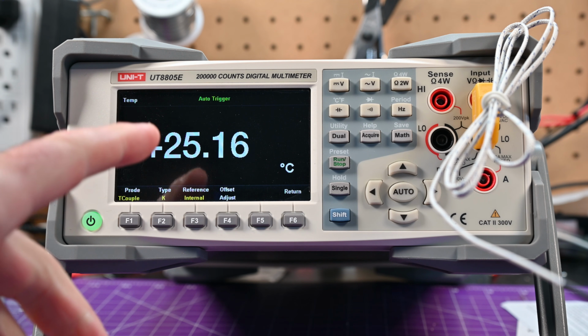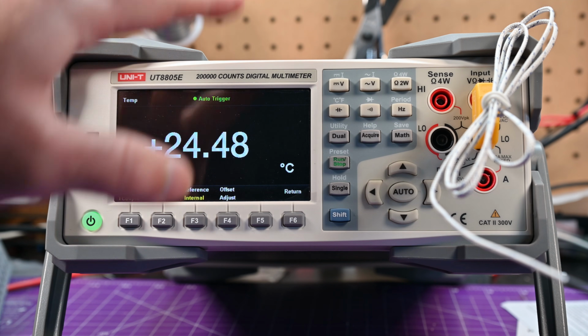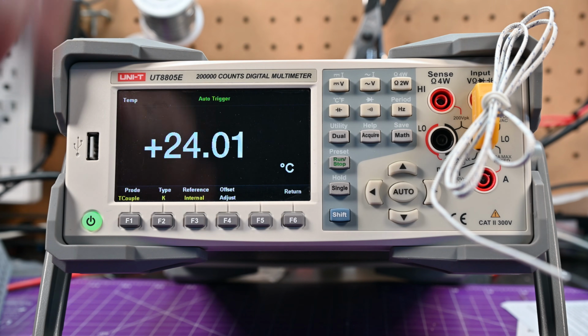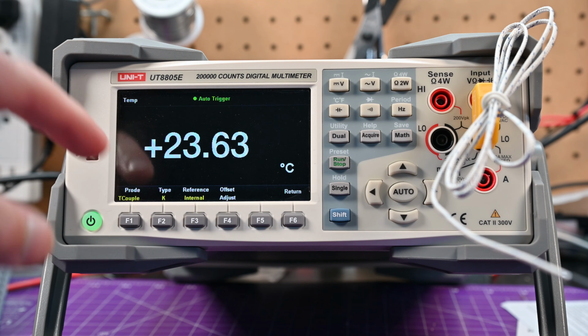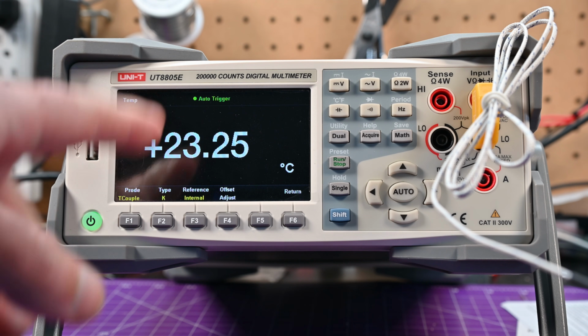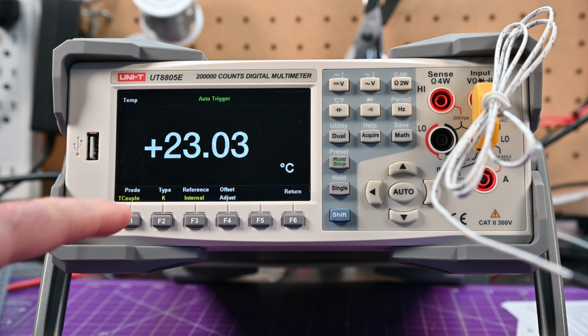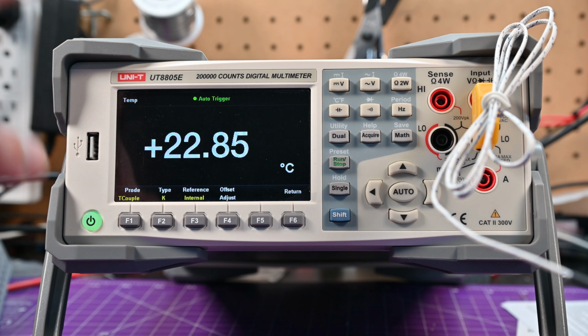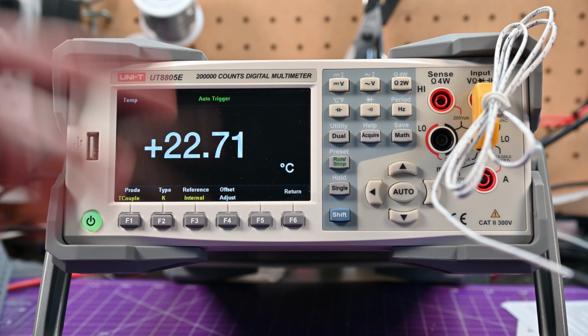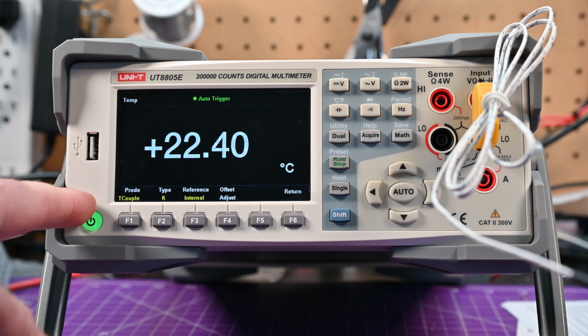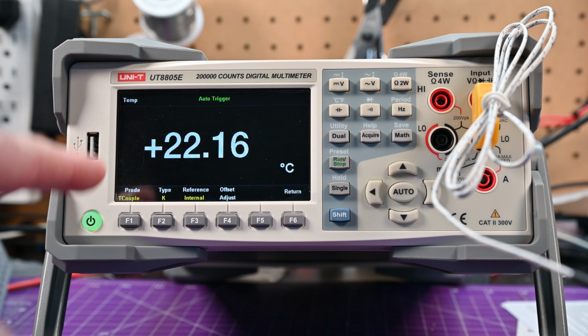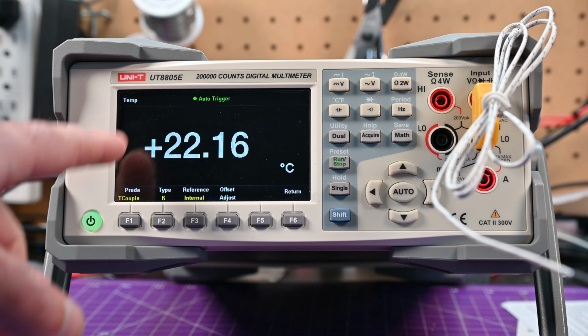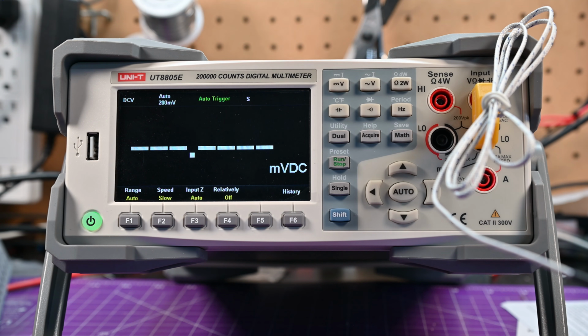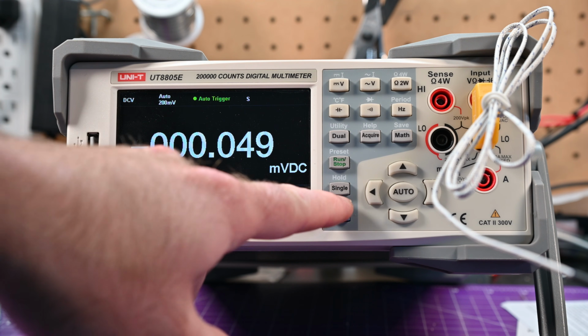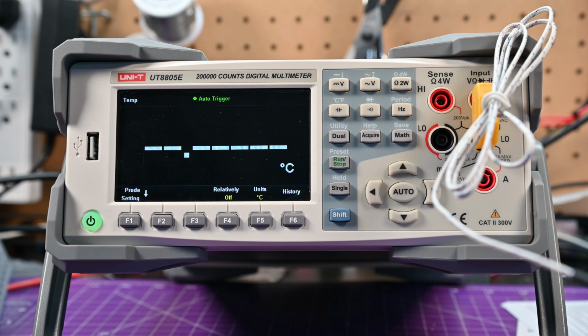Something to keep an eye on is that this thing is internally compensated, so this number should be as accurate as possible. But I actually set this to a K-type thermocouple before this video, and it didn't remember my setting after the power cycle. That means that very likely every time you go to temperature mode after a power cycle, you may have to set it again. Let's see if it'll just remember.